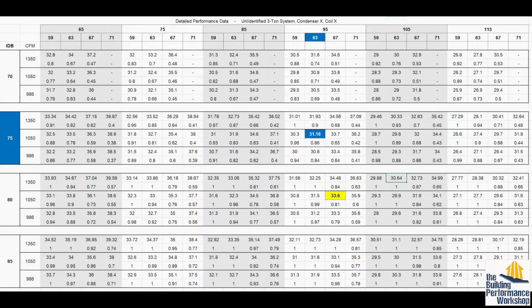If you have a duct system in conditioned space, by the way, and no ventilation air, the 80 degrees is what they're saying is going to be going through your system. That means the house is 80 degrees. That's nonsense. The number that's a little harder to understand is the wet bulb, but it is more important. They use 67 degree wet bulb. 67 degrees is 50% relative humidity if it's 80 degrees. If it's 75 degrees, 60+% relative humidity if you cool that air down to 75. I don't remember what the actual number is, but it is too humid, okay?